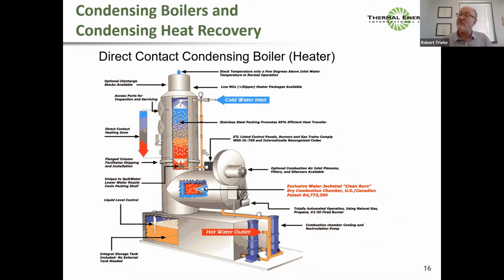So here I've got a burner and the burner is literally in a shroud underneath a shower of water. And so the flue gas comes out of that shroud, is in direct contact with a shower. It's like spraying a hose above a burner. And so the water that's heated is in direct contact and you get a hot water outlet. These devices are very cost effective because there's no pressure vessel here. But I'll talk more about the pros and cons later.